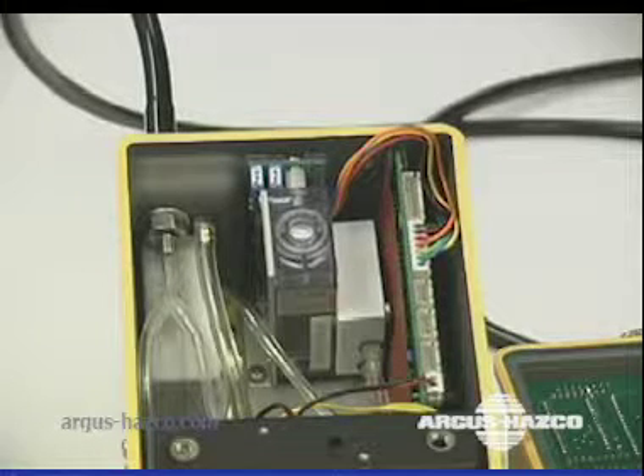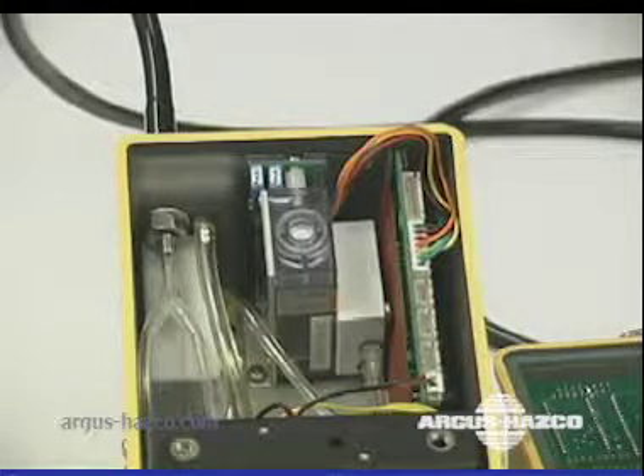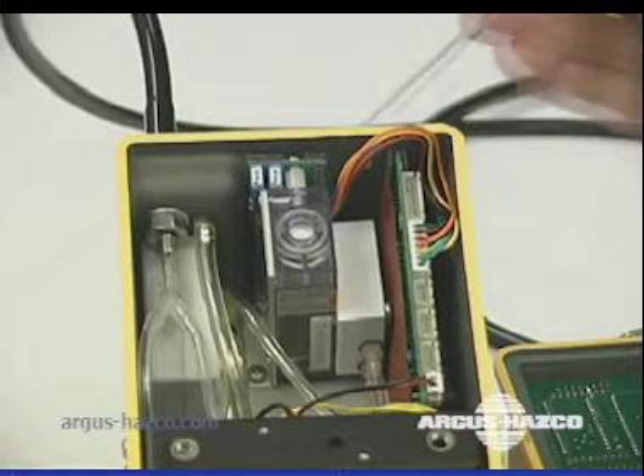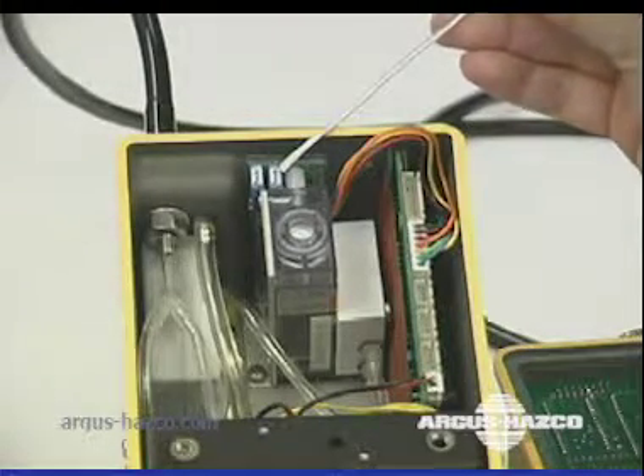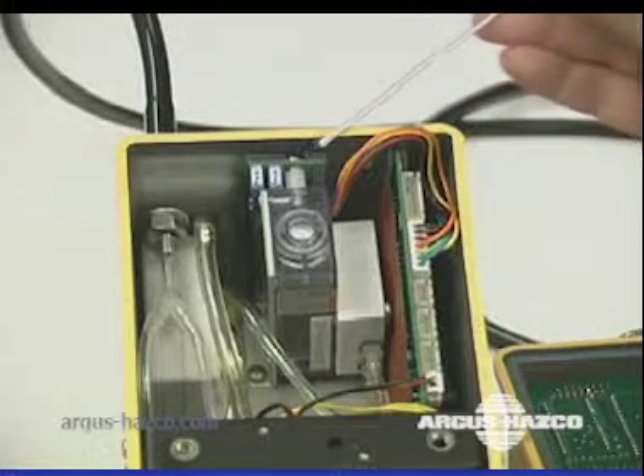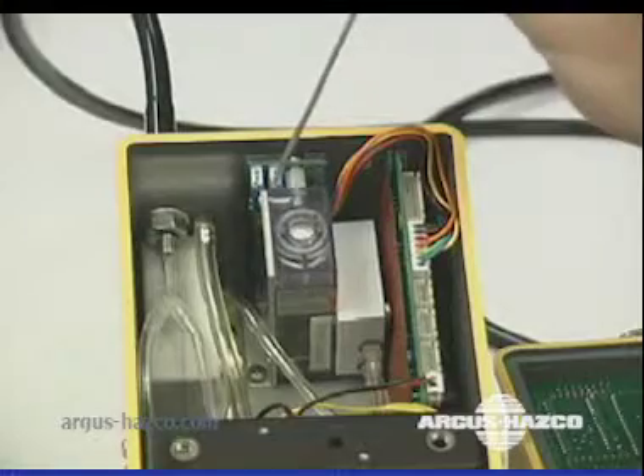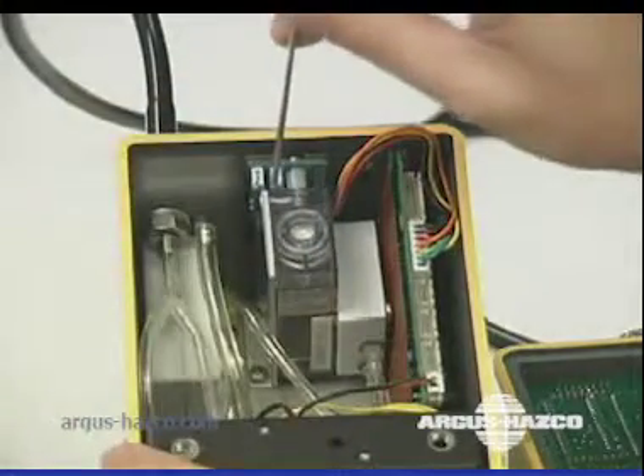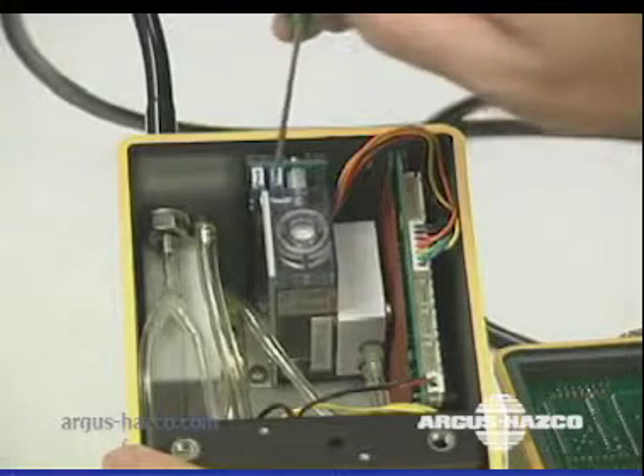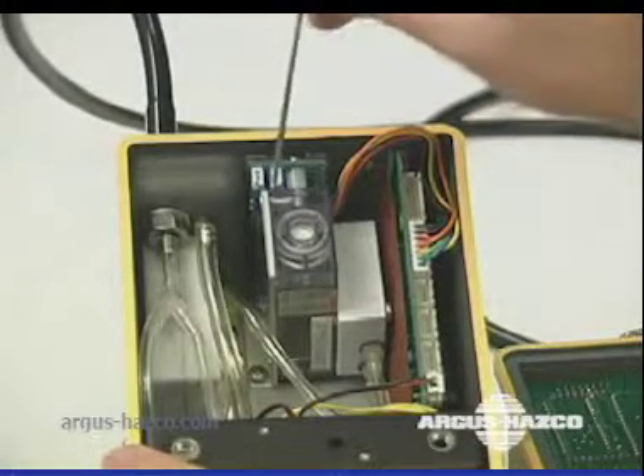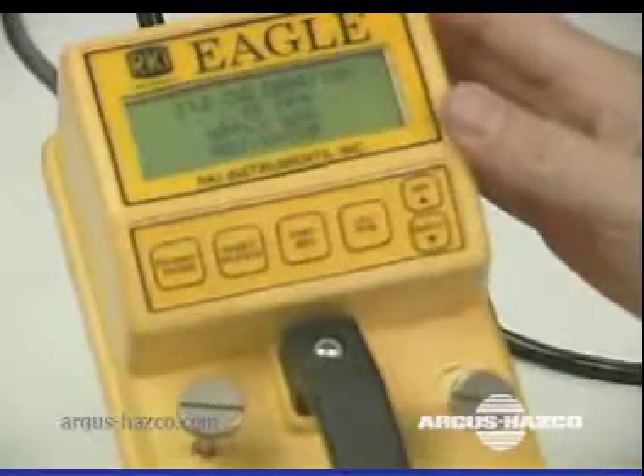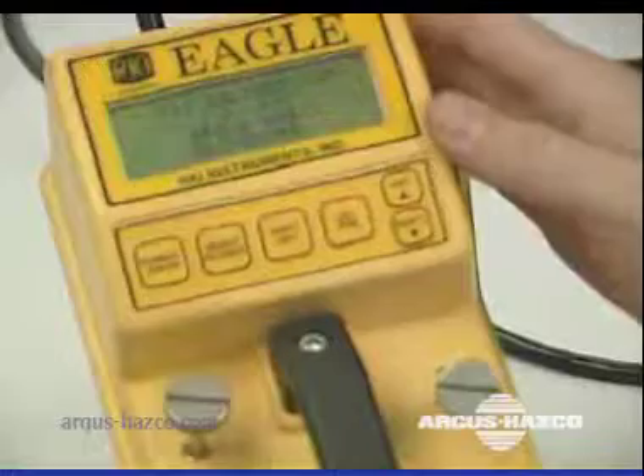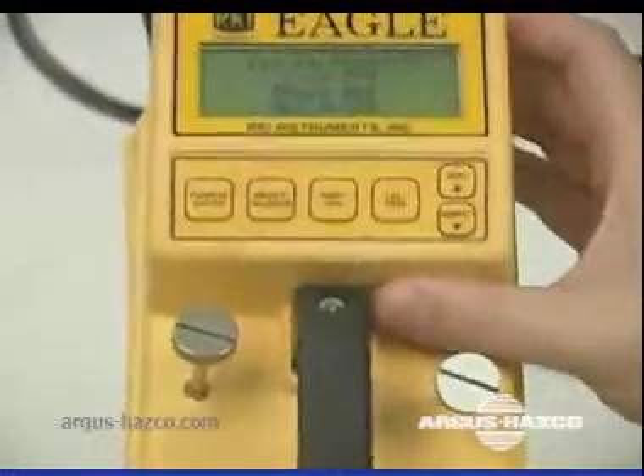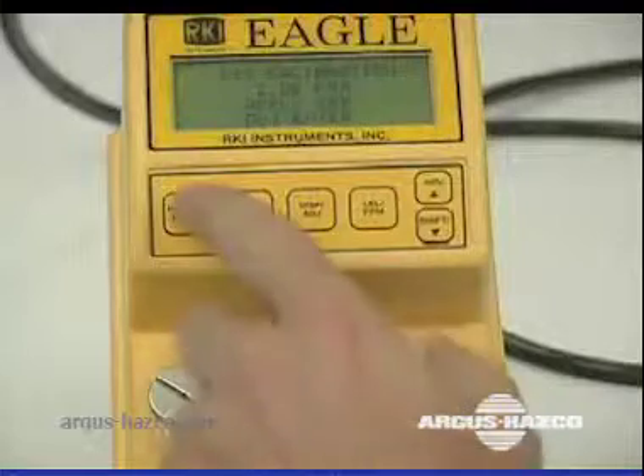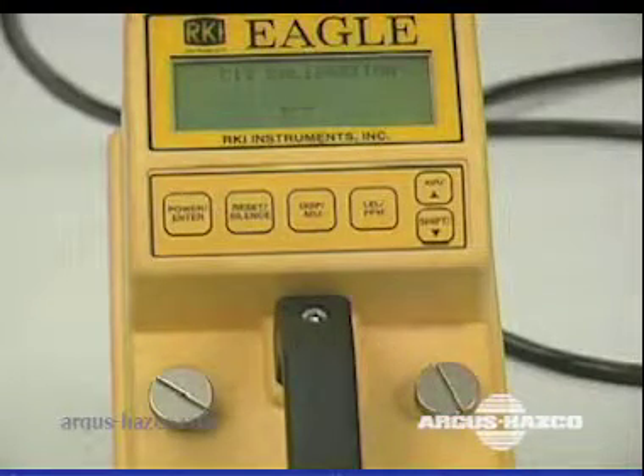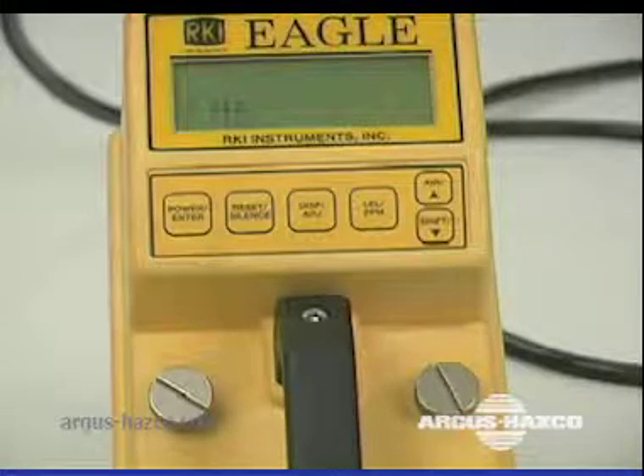To make adjustments with the sensor controls, first find the span control. The span control is located next to the sensor on the side closest to the front of the instrument. Adjust the sensor span control 1 turn and observe the display reading. Continue to adjust the span control until the display reading matches the concentration of the calibration cylinder. Press the Enter button to set the span value. Single calibration end will then display and you'll return to the single calibration menu.